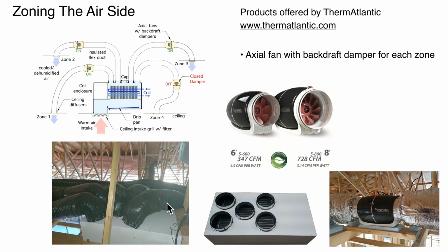They're taking insulated flex duct from the connections on this unit. And each of those flex ducts contains a fan. And the operation of that fan is coordinated with a zone thermostat. So in this case, you've got 4 zones of cooling, but you're doing the zoning on the air side as opposed to doing it on the hydronic side.